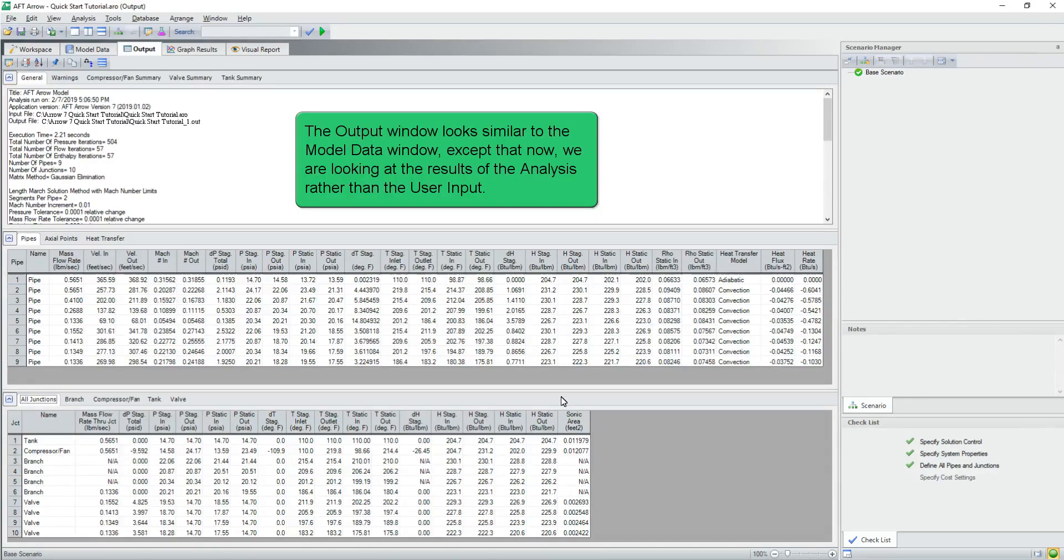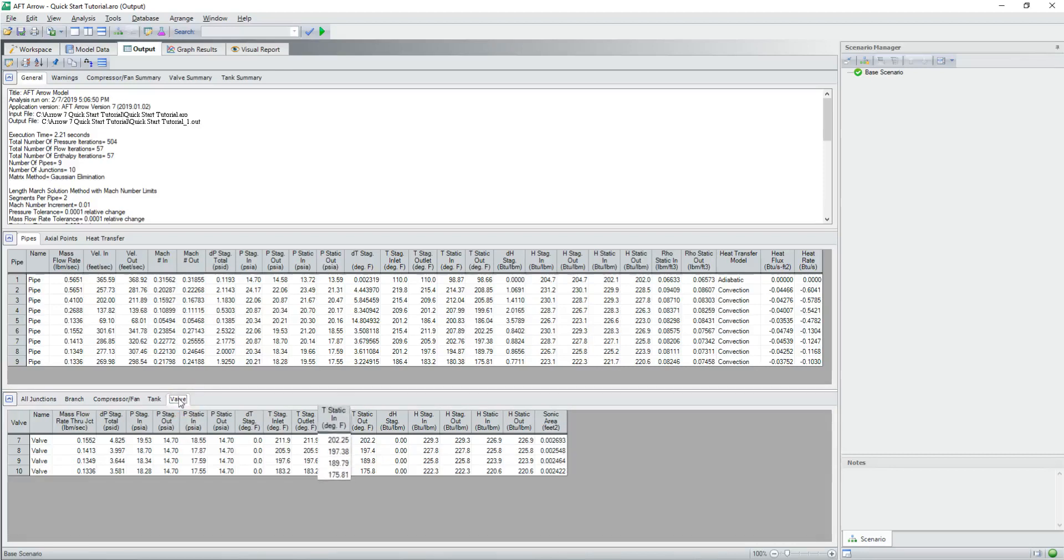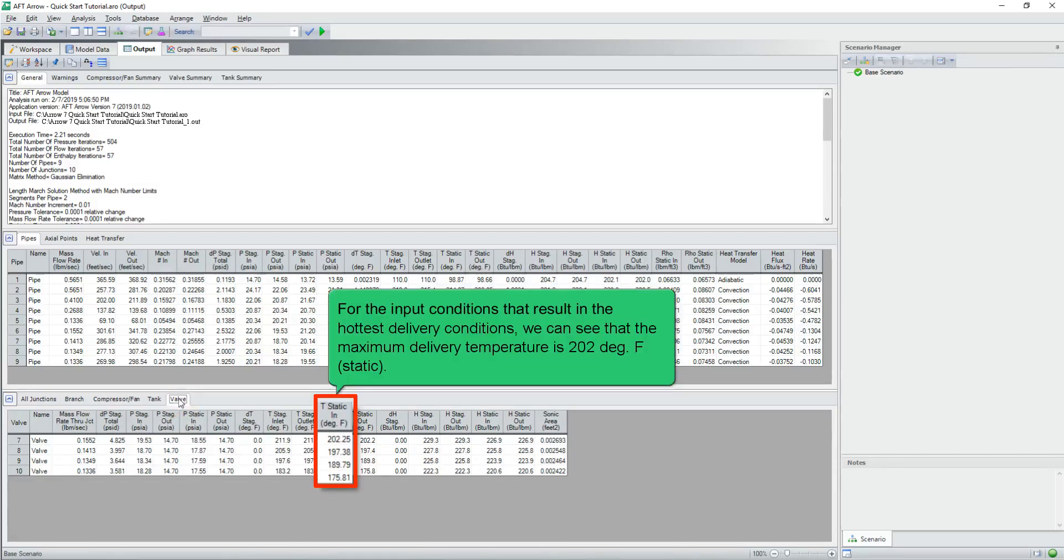The output window looks similar to the model data window, except that now we are looking at the results of the analysis rather than user input. For the input conditions that result in the hottest delivery conditions, we can see that the maximum delivery static temperature is 202 degrees Fahrenheit.